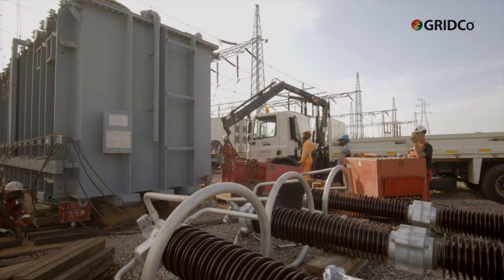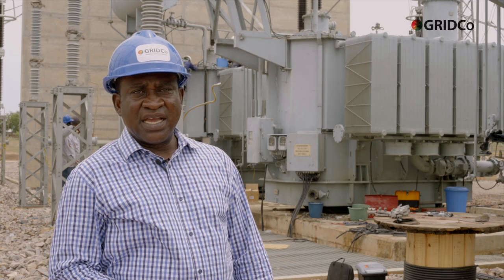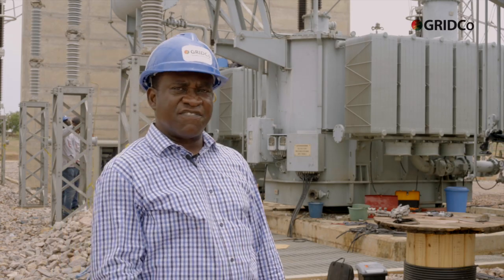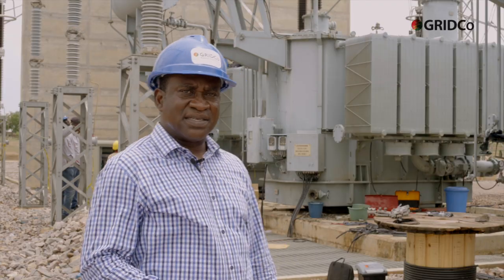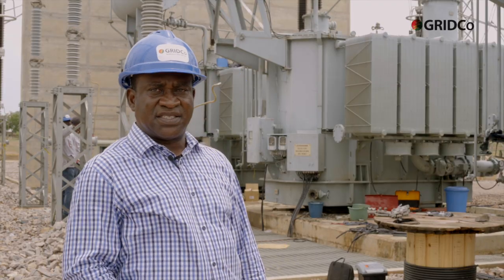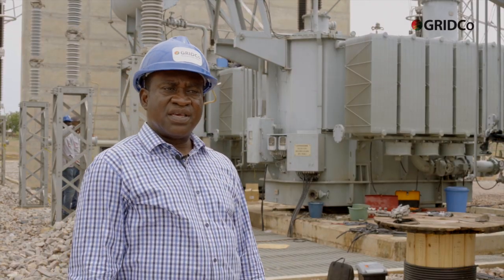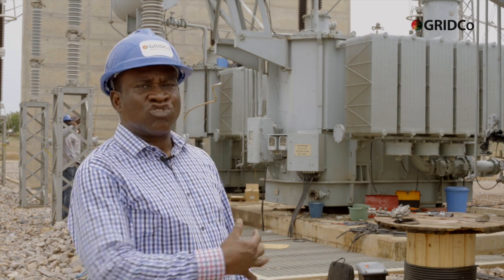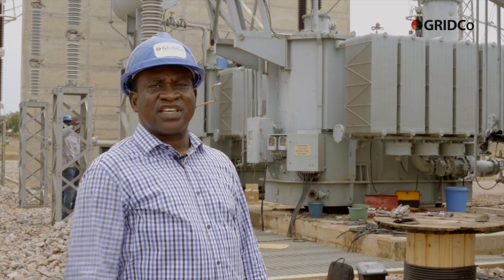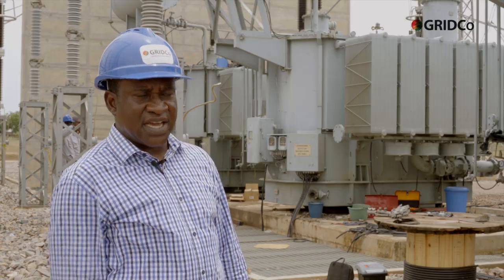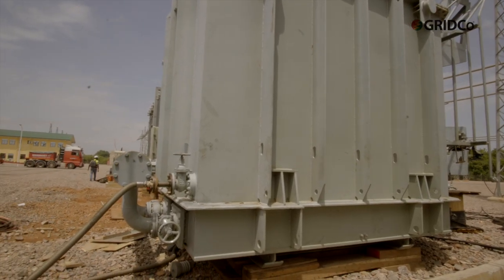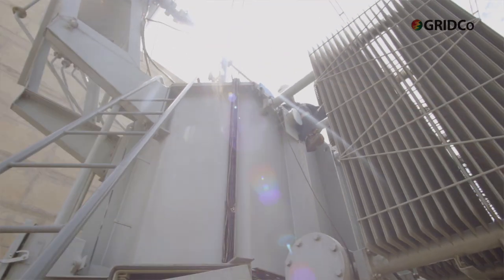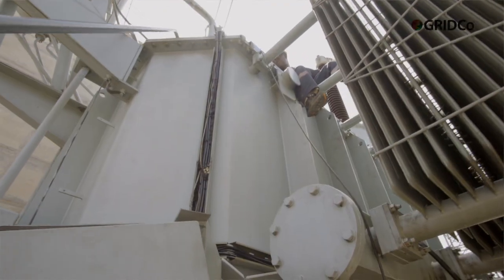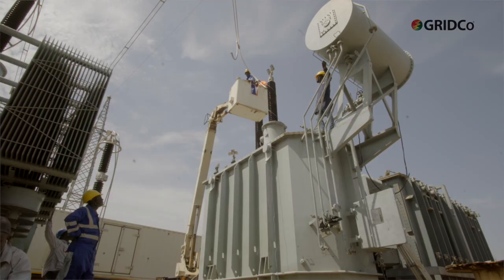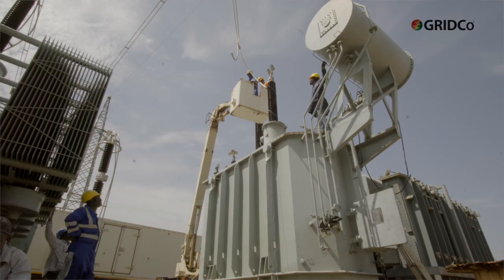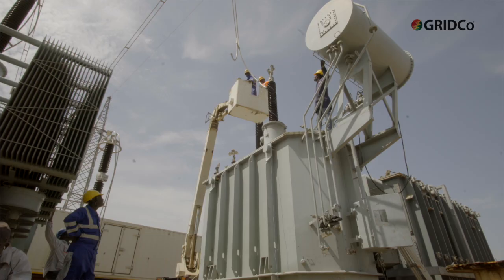In order to ensure reliability and continuity of power supply to Burkina Faso, it became apparent that a transformer with the same capacity, which is 200 MVA, is looked for and installed in its position while the faulted transformer is being worked on in China. Management was able to locate a transformer which has been installed at Elubu in Western region, decommissioned and transported from Elubu to Nayagnia Substation.